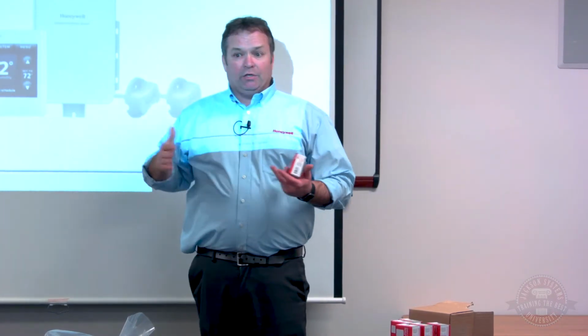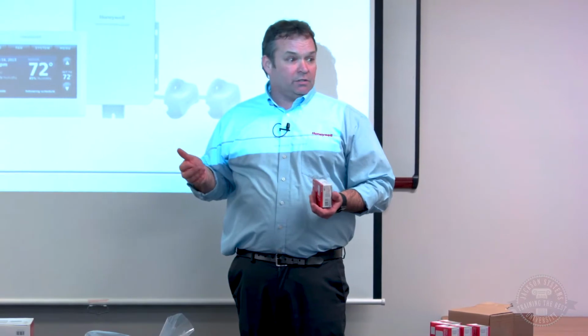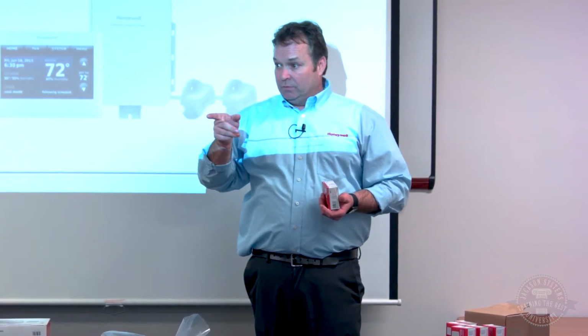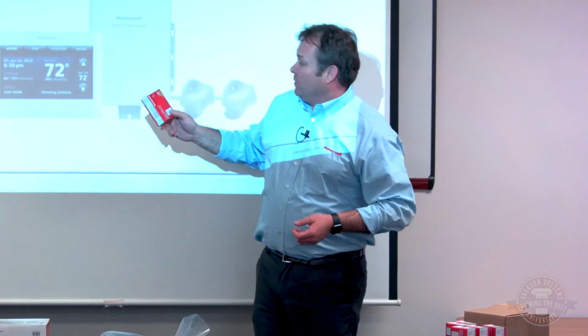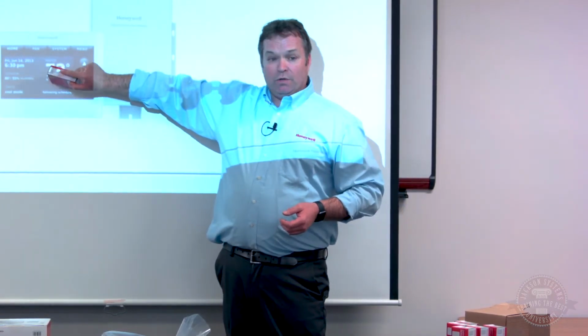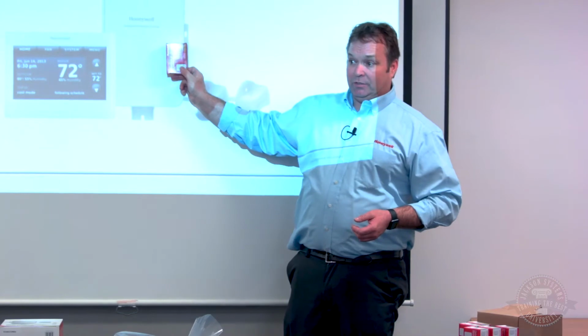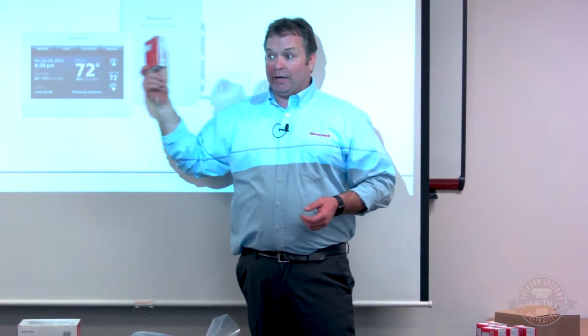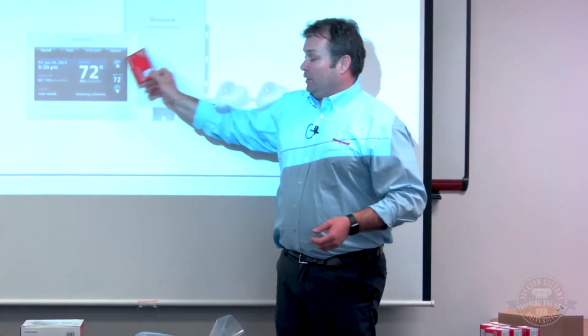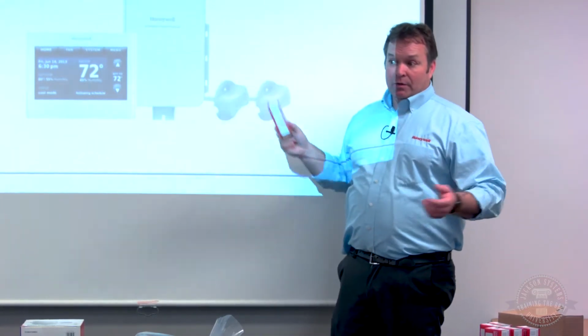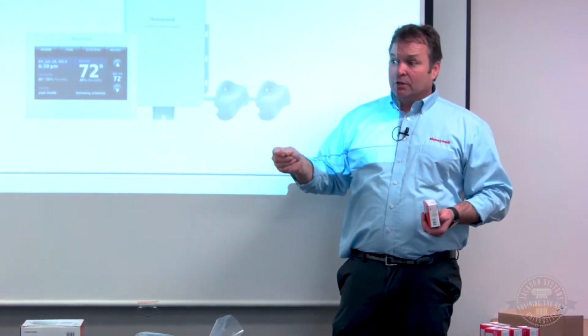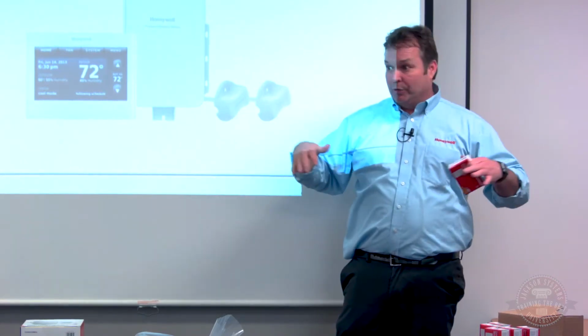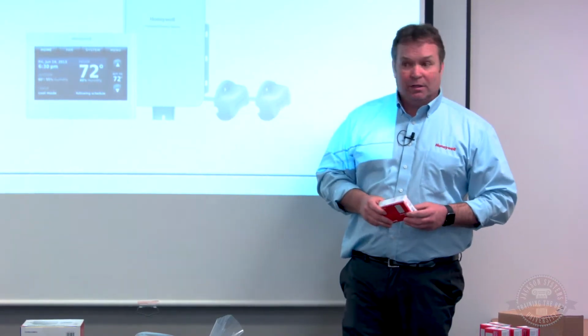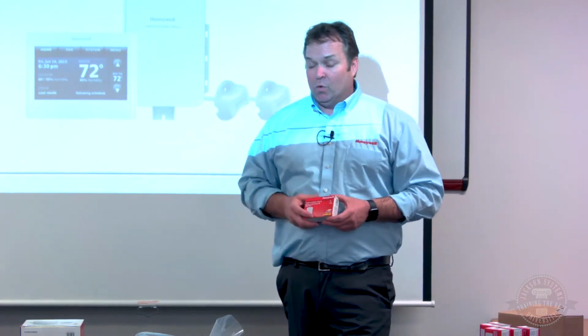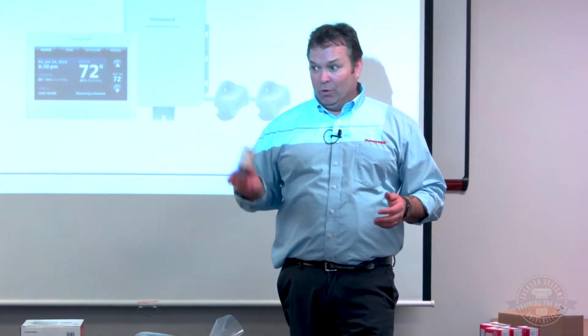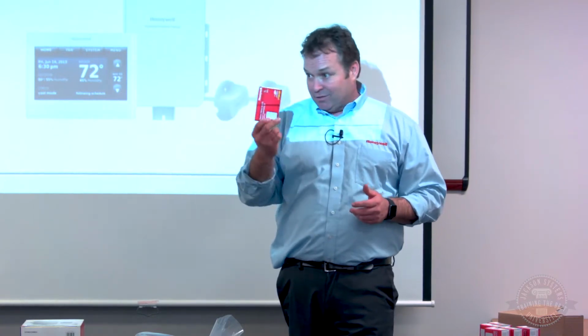The nomenclature of our thermostat—that's a YTHX, the X meaning yes, you can have multiple. If the thermostat is one of the sensors, I can add 5 of these. If the thermostat sensor is disabled, I could add 6 and do averaging. I could do 1, I could do 2—it doesn't matter. The old hardwired ones, you had to do 4 or 9 because we were doing square roots. Wireless eliminated all that square root, series-parallel wiring that just stinks. If you've ever done that before, you'll love this.